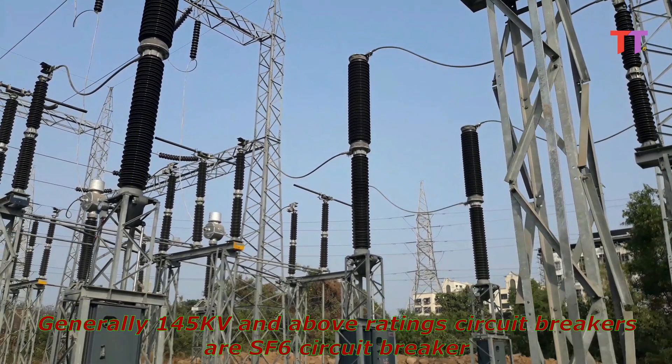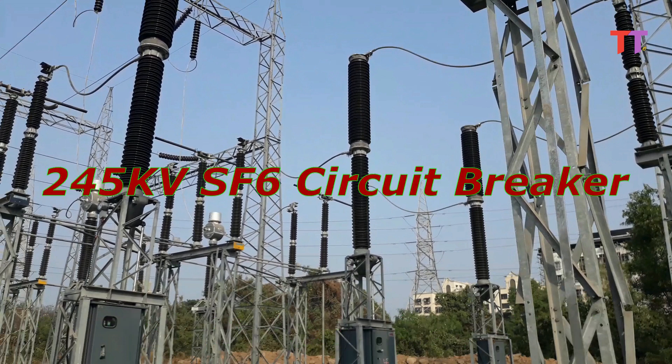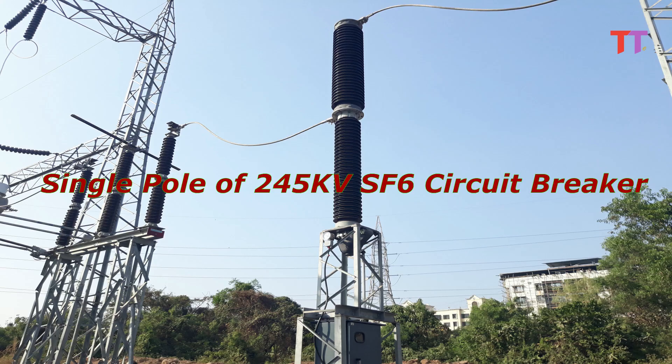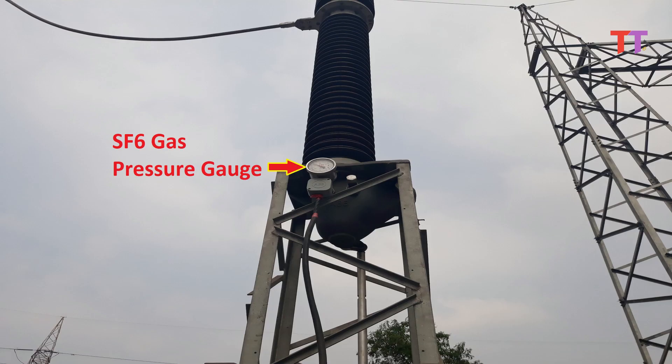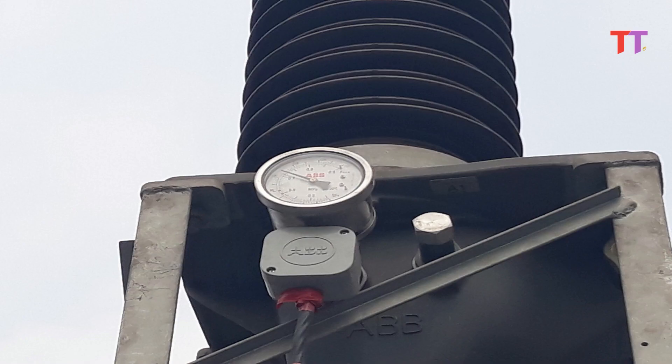Generally 145 kV and above rating circuit breakers are SF6 circuit breaker. This is 220 kV SF6 circuit breaker and this is single pole of circuit breaker. These are top and bottom connection palms where conductors are connected. This is SF6 gas pressure gauge to monitor SF6 gas pressure inside interrupter.